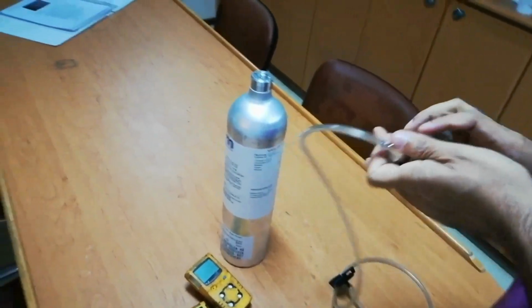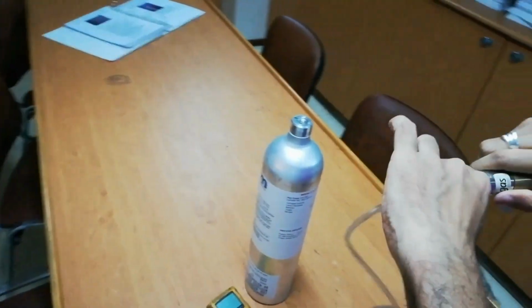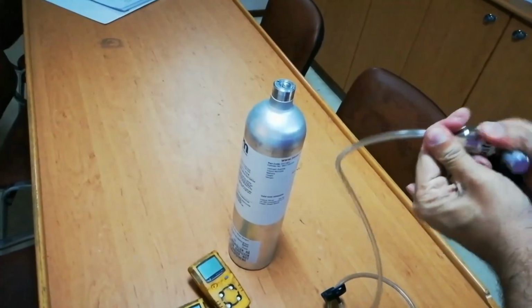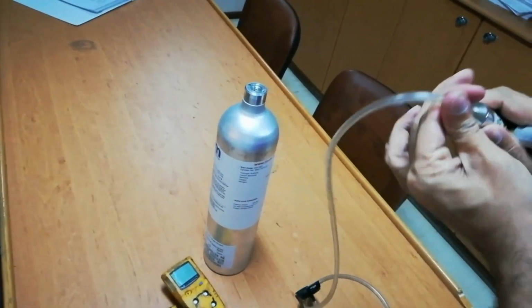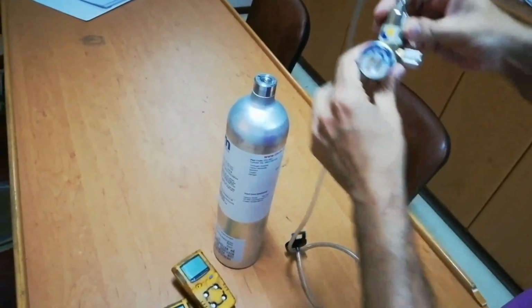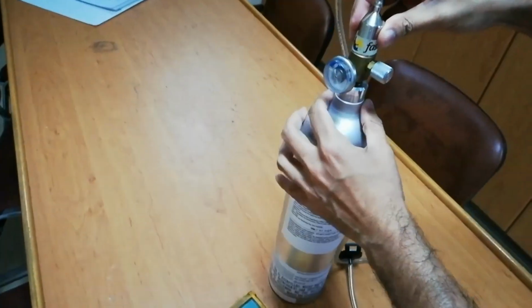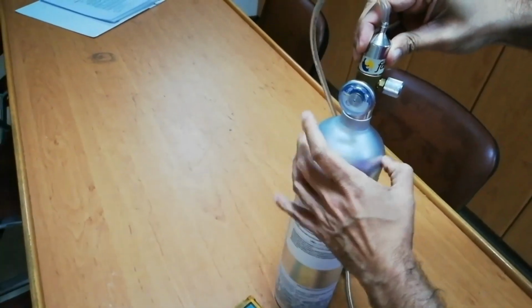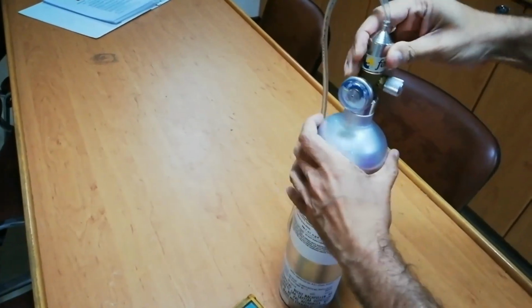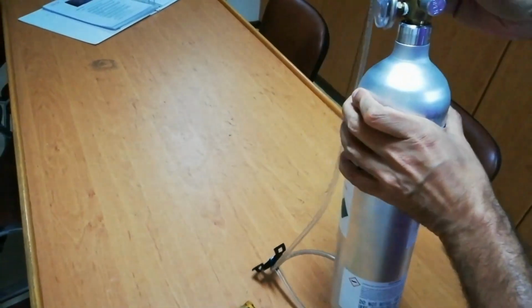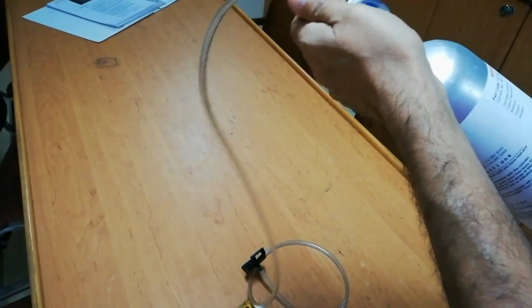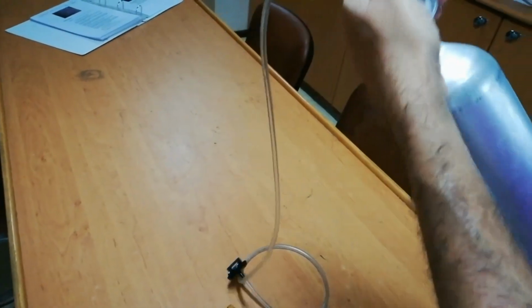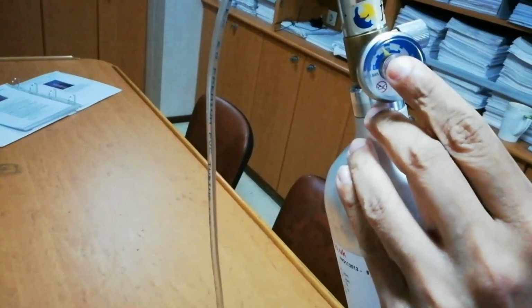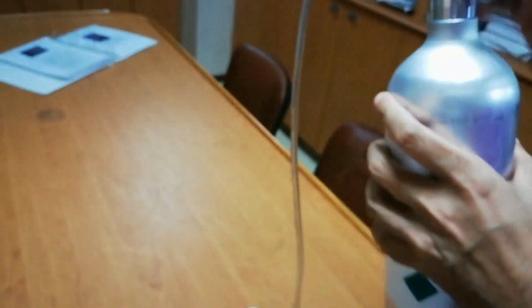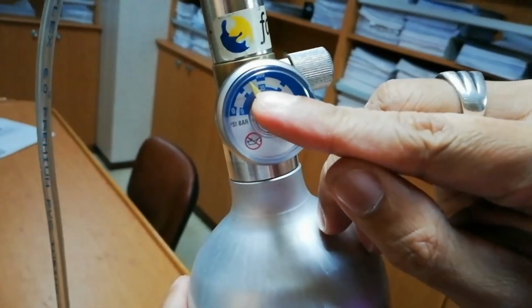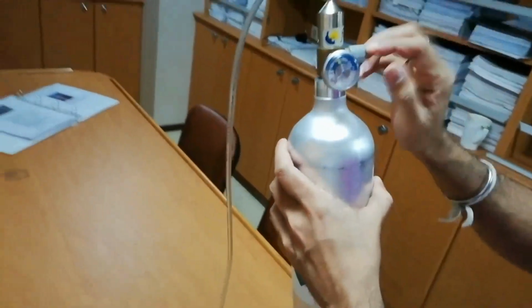Now I am going to connect this regulator to the calibration hose. First I connect the 0.5 liter per minute fixed flow regulator, and now I am connecting this regulator to the span gas cylinder. Make sure you have positive pressure. First we have to check the capacity inside the cylinder. Now you can see here we have positive pressure. Now we are going to do the calibration.